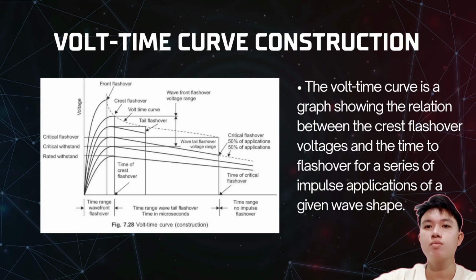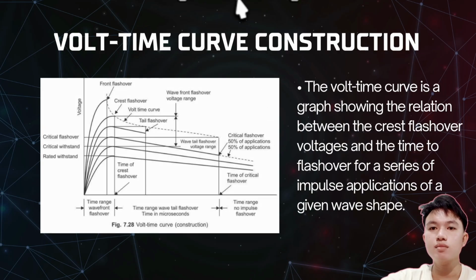The volt time curve is a graph showing the relation between the crest flashover voltages and the time to flashover for a series of impulse applications of a given wave shape. In simple terms, it shows how much voltage an insulator can withstand before failing, depending on how long that voltage is applied. So the diagram illustrates the volt time VT curve construction, a fundamental concept in high voltage engineering used to determine the insulation strength of electrical equipment against lightning or switching surges.